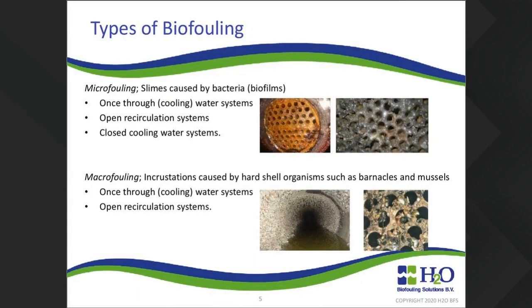Generally, there are 2 types of biofouling species. Microfouling, that's bacteria which form a bacterial slime layer, which is called a biofilm. This type of fouling happens in all 3 different kinds of cooling water systems: a once-through cooling water system, an open recirculation system with a cooling tower, or a closed loop water system. In cooling towers, there is an additional risk where the slime layers can foul the packing of the cooling tower.